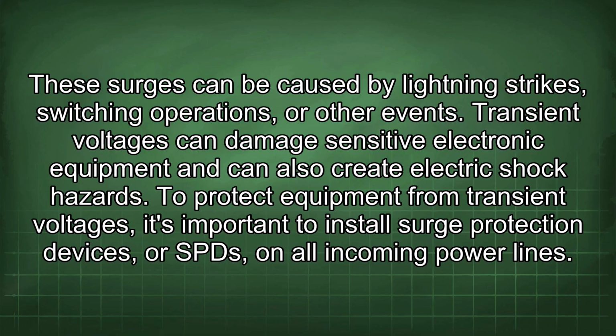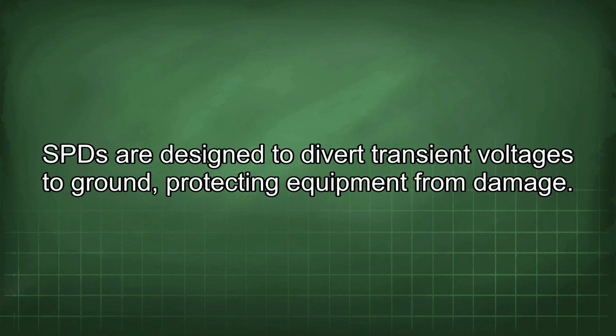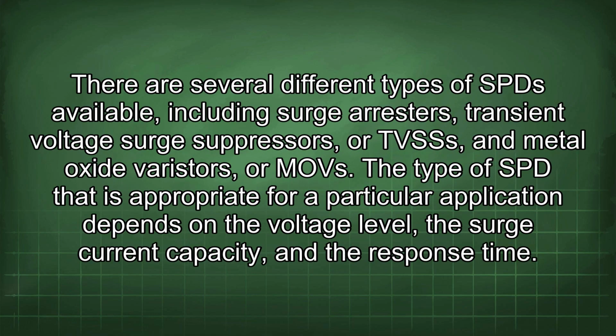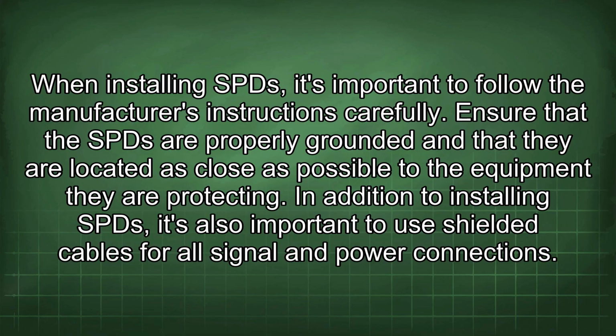To protect equipment from transient voltages, it's important to install surge protection devices, or SPDs, on all incoming power lines. SPDs are designed to divert transient voltages to ground, protecting equipment from damage. There are several different types of SPD available, including surge arresters, transient voltage surge suppressors, or TVSSs, and metal oxide varistors, or MOVs. The type of SPD that is appropriate for a particular application depends on the voltage level, the surge current capacity, and the response time. When installing SPDs, it's important to follow the manufacturer's instructions carefully.